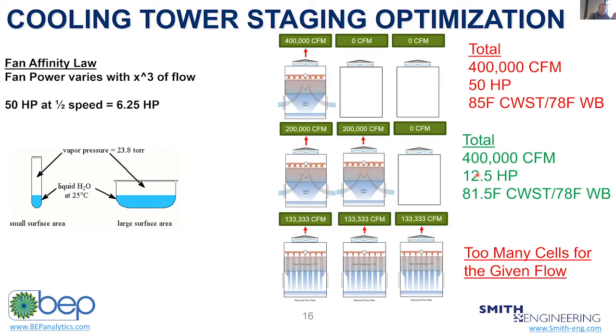Running these two fans, I'm at 12.5 horsepower total. The trick is I've doubled the heat transfer surface area. So that's a somewhat linear reduction in approach temperature.